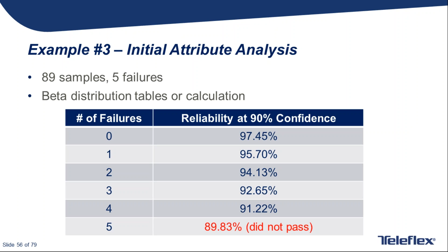So in the improved analysis, I wanted it to be as objective as possible and start from scratch. Two non-negotiable principles were that the acceptance criteria had to be risk-based and that variable data could be used. Why not? Each of the data points had a number, not just a pass-fail decision. There was nothing that could be done about the sample size or the data itself at this point, but let's see if a statistics person can add value after the fact. So the applicable risk analysis took us to a severity rating of 2 for this failure mode.